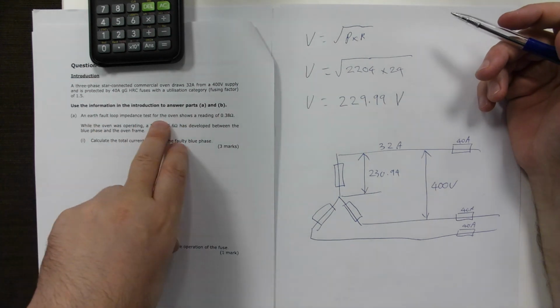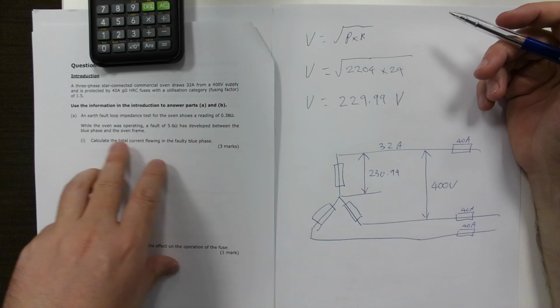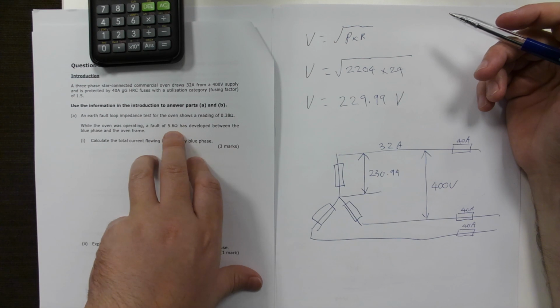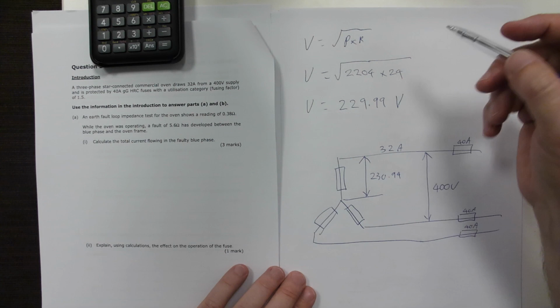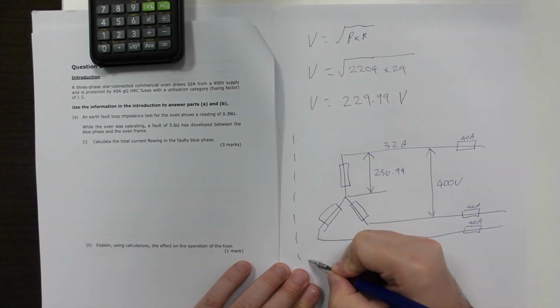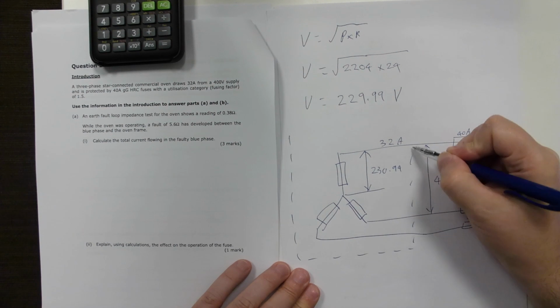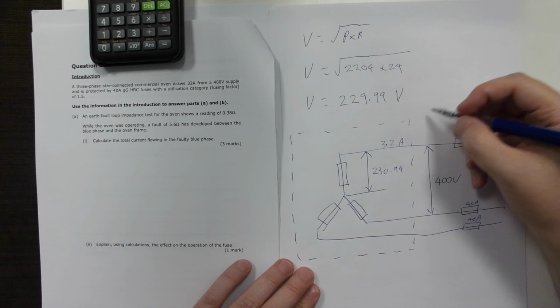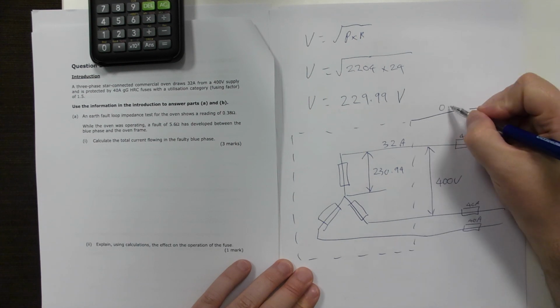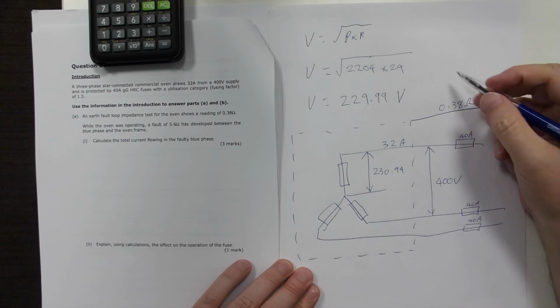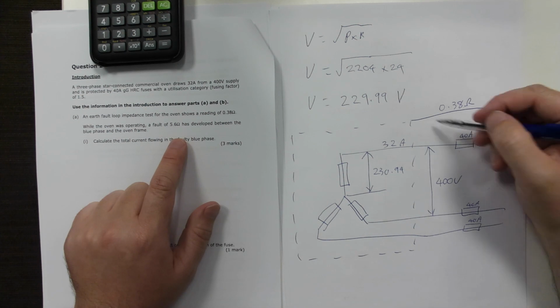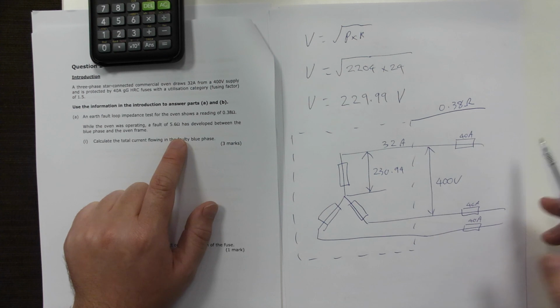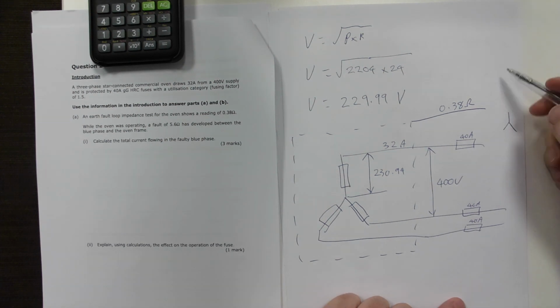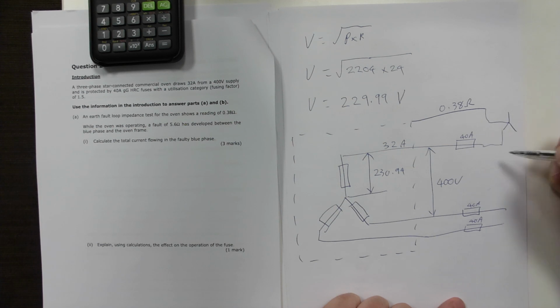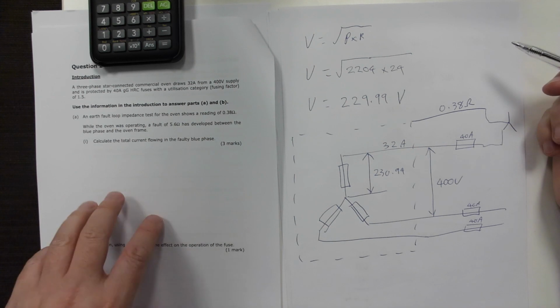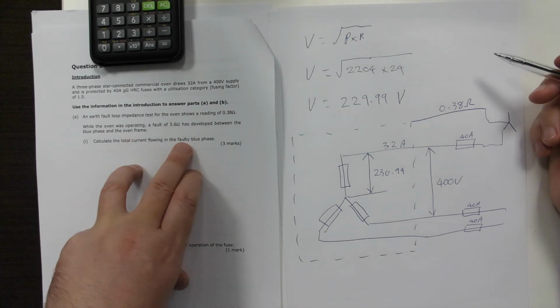So, an earth fault loop impedance test for the oven shows a reading of 0.38 ohms. While the oven was operating, a fault of 5.6 ohms has developed between the blue phase and the oven frame. So we're dealing with the oven frame, and this will be earth. And we know that we've got a 0.38 earth loop impedance. That's not just the earth wire, it's actually also combined with the phase coming from the star transformer that's feeding it. So that comes off there, and then these two can be the other two. So they want us to calculate the total current flowing in the faulty blue phase.